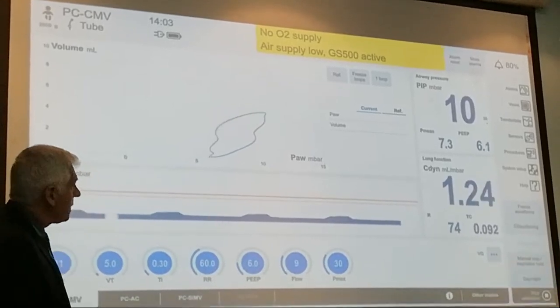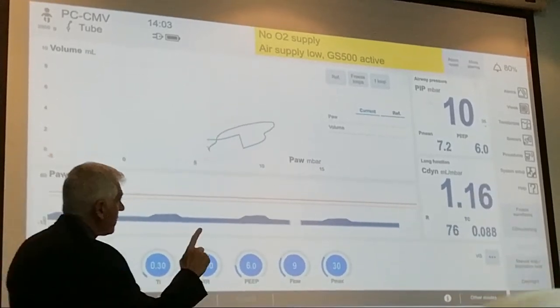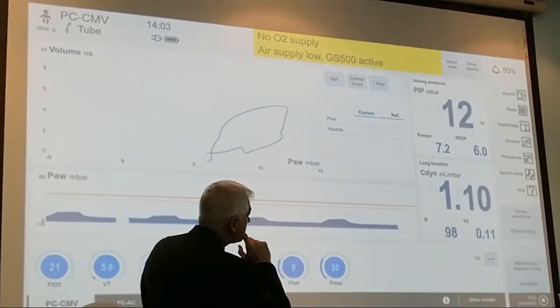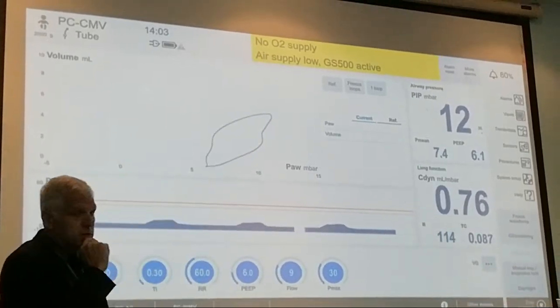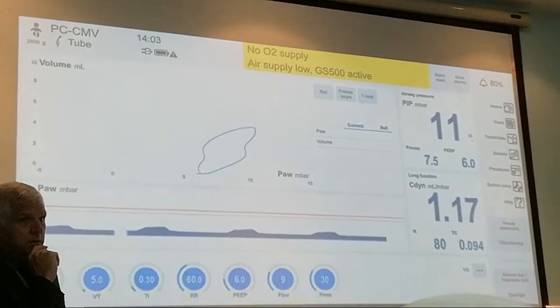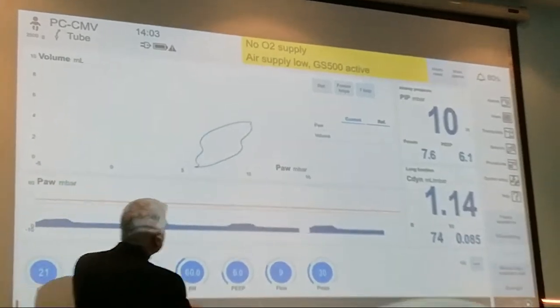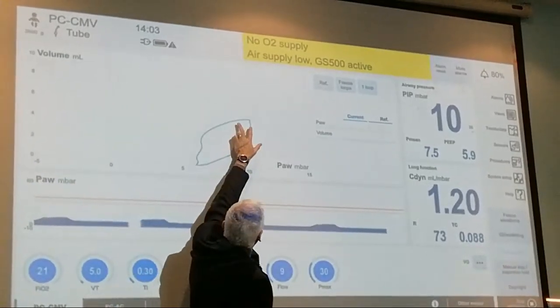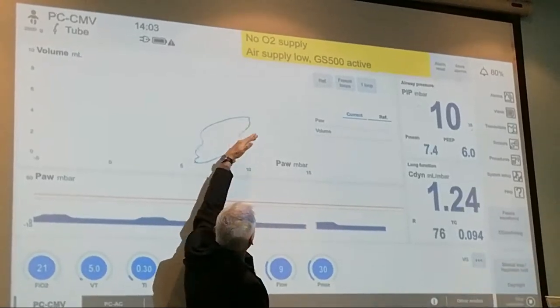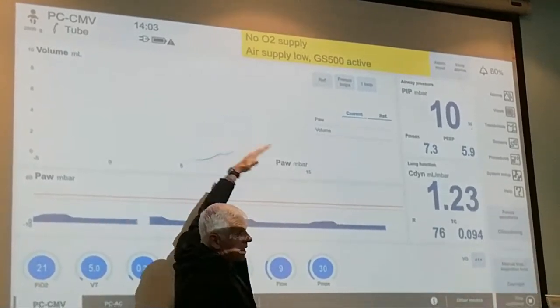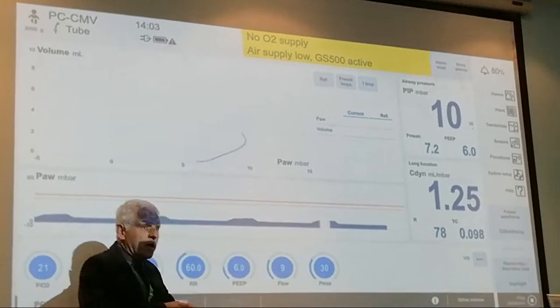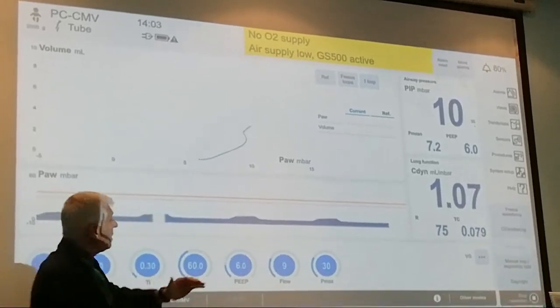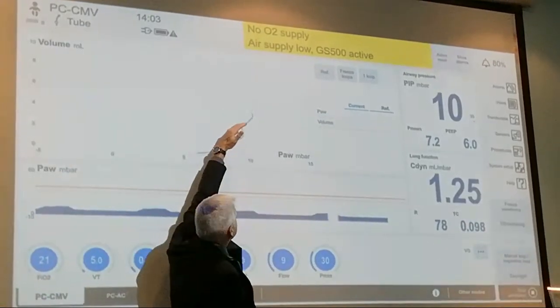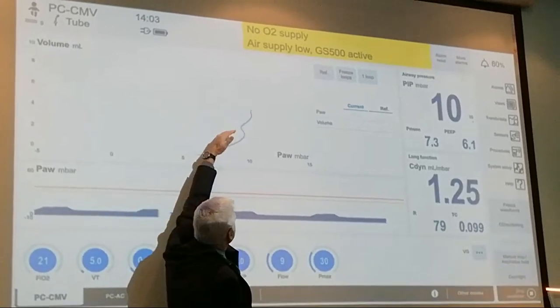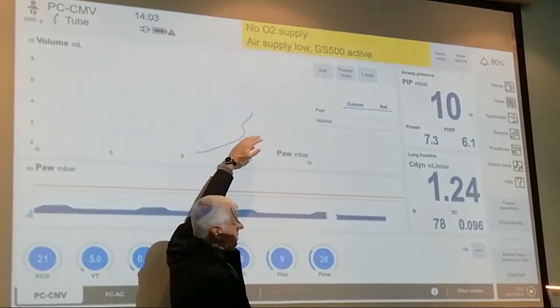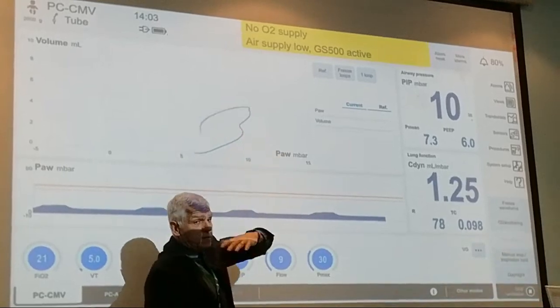So now, the other number that is important to watch is the C20 versus total compliance. You understand what that is? Basically, the machine is looking at the last 20% of the compliance curve and dividing that by the total compliance. In a normal situation, you shouldn't have a difference. It should be the same. When the last 20% of that compliance curve is significantly less than the total compliance, it means that you have over-distension.